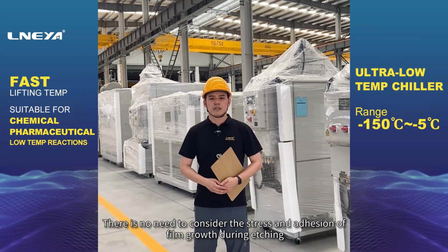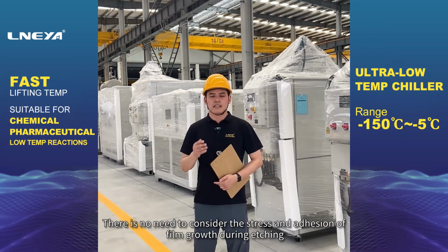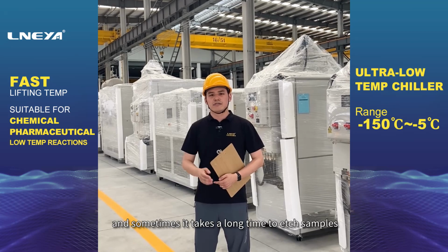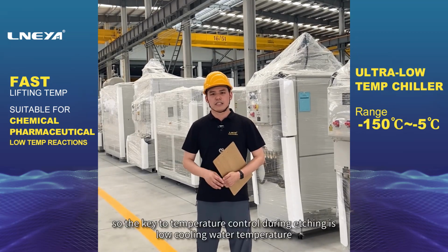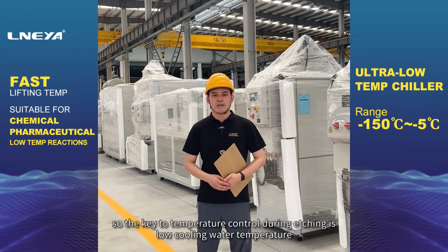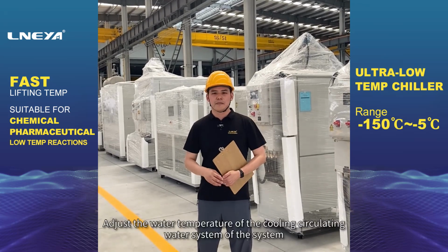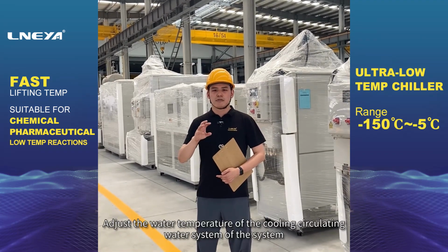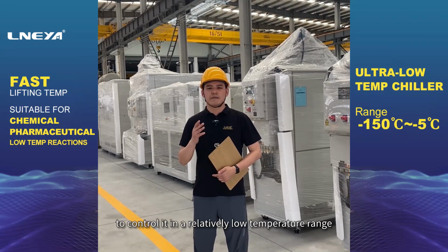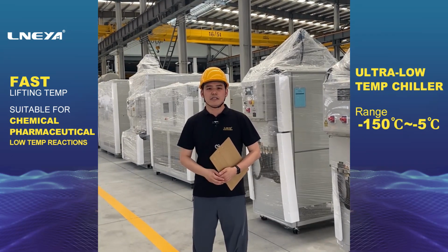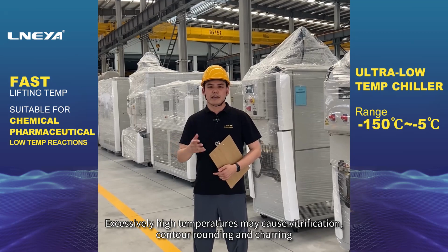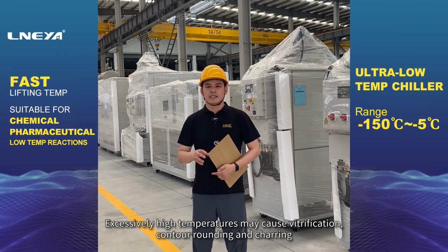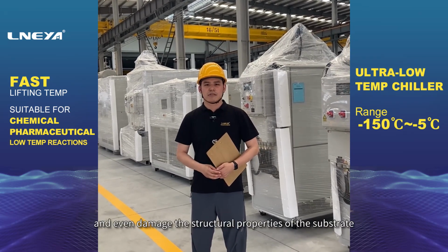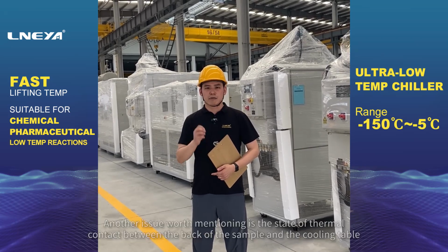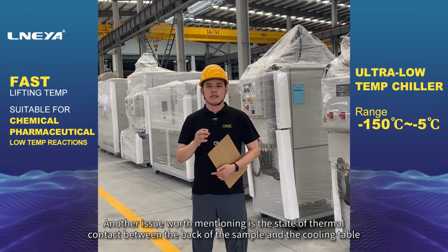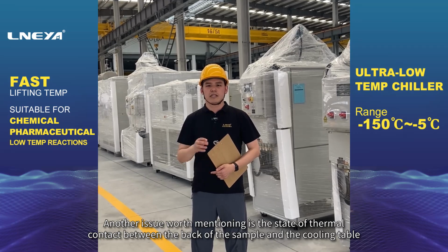There is no need to consider the stress and adhesion of film growth during etching, and sometimes it takes a long time to etch samples, so the key to temperature control during etching is low cooling water temperature. Adjust the water temperature of the cooling circulating water system of the system to control it in a relatively low temperature range. Excessively high temperatures may cause vitrification, contour rounding and charring, and even damage the structural properties of the substrate. Another issue worth mentioning is the state of thermal contact between the back of the sample and the cooling table.